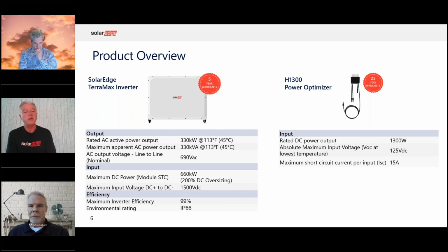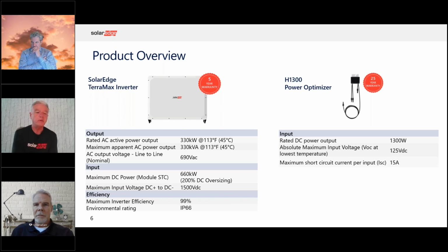Again, it's a 1500 volt DC rated inverter, which is what you would see in these larger ground mount projects, which are 1500 volt DC systems. Its max DC to AC ratio is 200%, so you can oversize it with up to about 660 kilowatts on the 330 kilowatt inverter. And it's highly efficient.